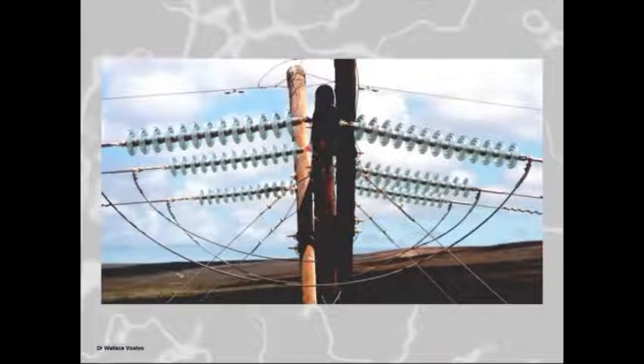And now what they're saying is, oh no, Wallace, you see, the problem here is an air breakdown, because of these conductive fogs. Now remember that these fogs didn't occur during the time when we had all these flashovers, okay? But now according to them, it's these fogs. It's a conductive fog, reducing the breakdown strength of the air gap, and that is why. So they wanted me to do laboratory tests and so on, and then put insulator sleeving over these jumpers to prevent this conductive fog flashover.